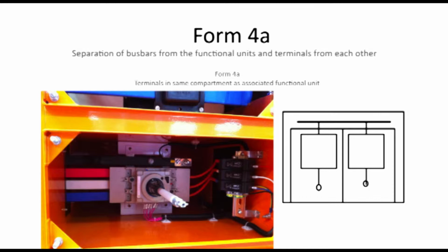So just quickly, there is no Form 2, there is no Form 3, there is no Form 4. It's 2A or B, 3A or B, or Form 4A or B. I've read on many occasions since 3439 was first published that a Form 3B switchboard is specified. The problem is a Form 3B switchboard to the current 3439 standard is not a fully separated design.